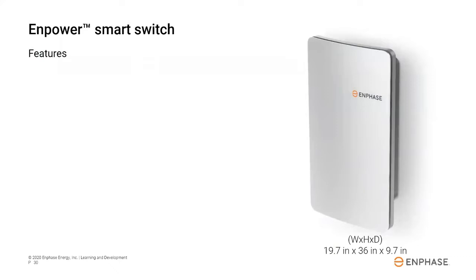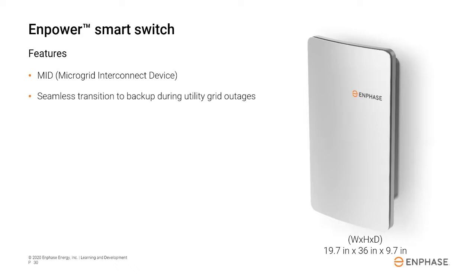The Enpower Smart Switch is the equivalent of the Tesla Powerwall gateway, and its primary job is to disconnect the home from the utility grid in the event of a grid outage. It's classified by the NEC as a microgrid interconnect device, and it's a required component for any of our systems that are providing backup power. If there is a grid outage, it disconnects within 12 to 15 milliseconds, extremely quickly, and the microgrid is instantly formed by the Encharge batteries. The response is so fast that clocks and devices typically don't even need to be reset, like microwaves.